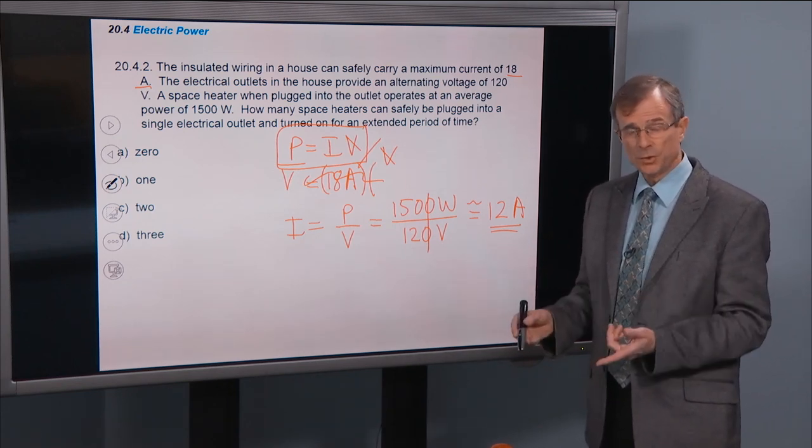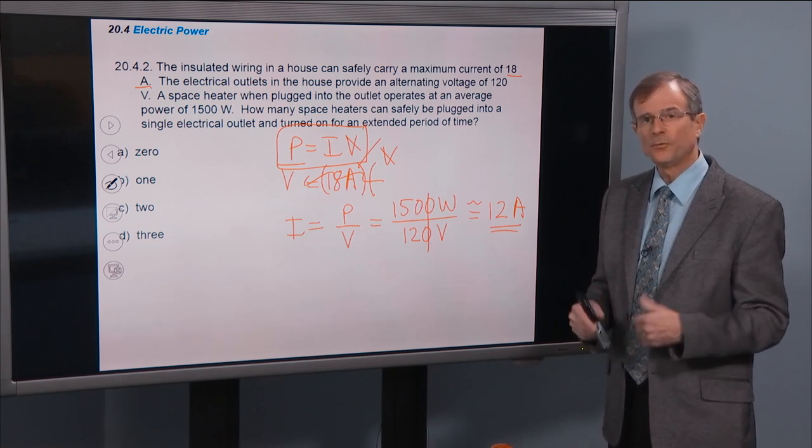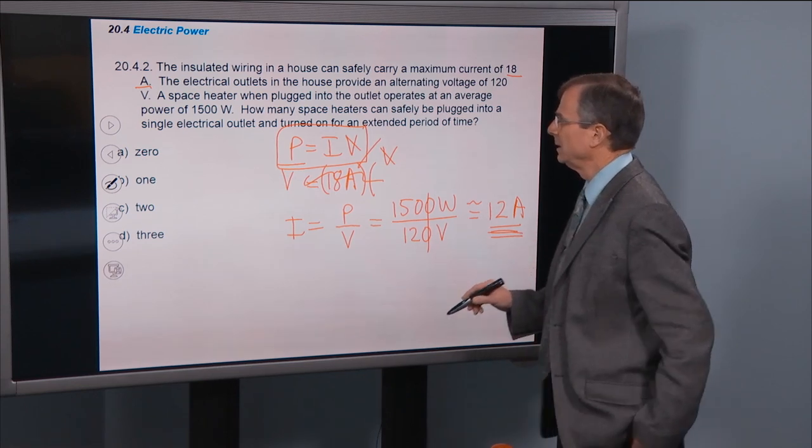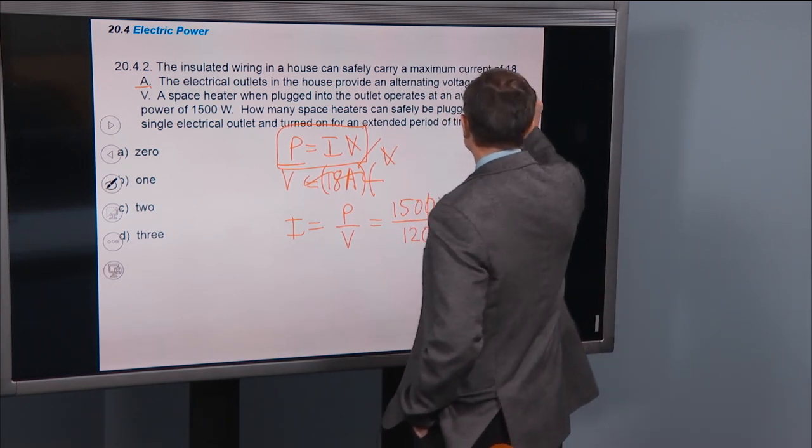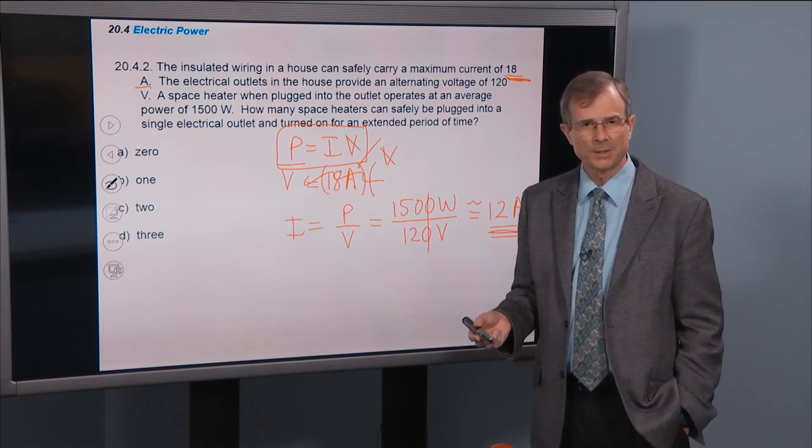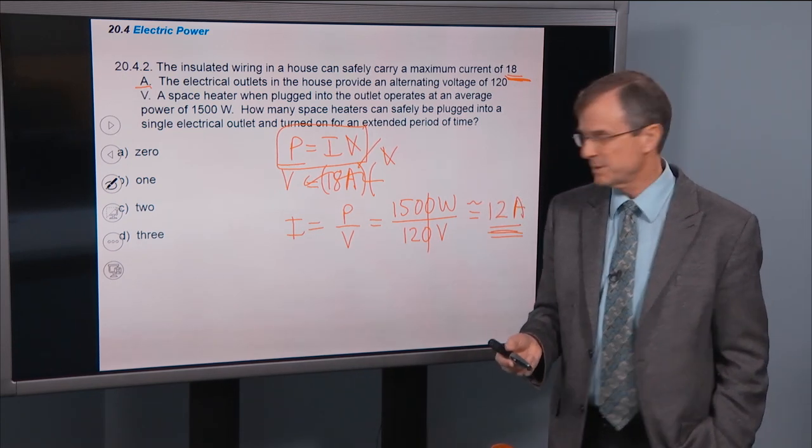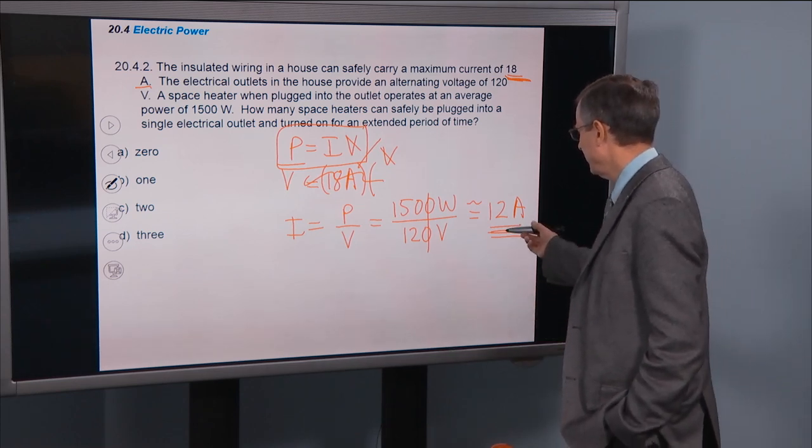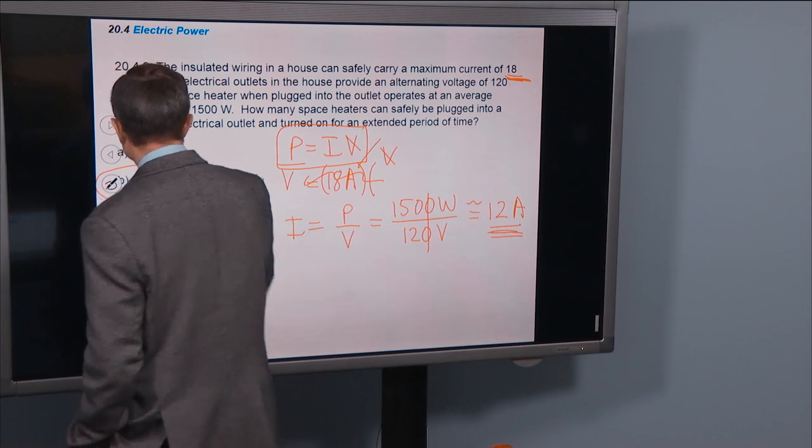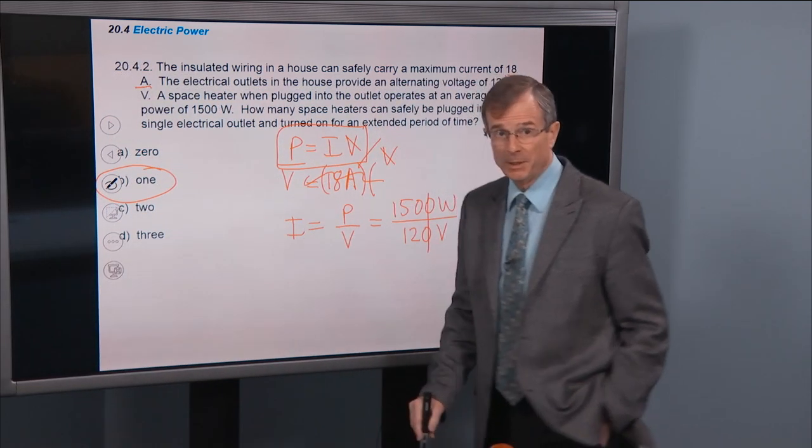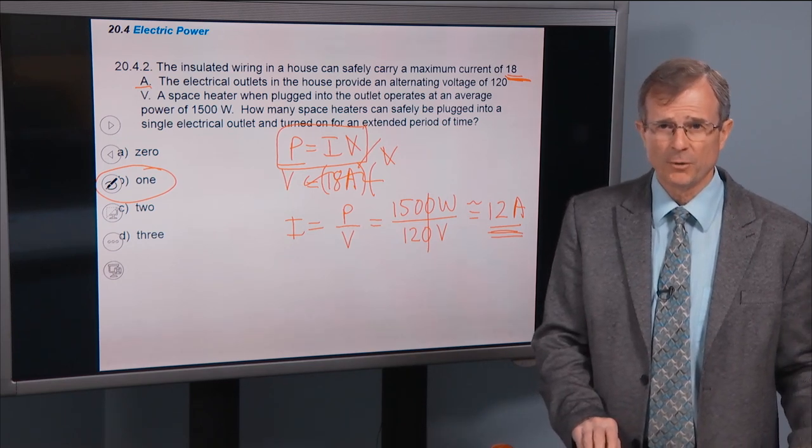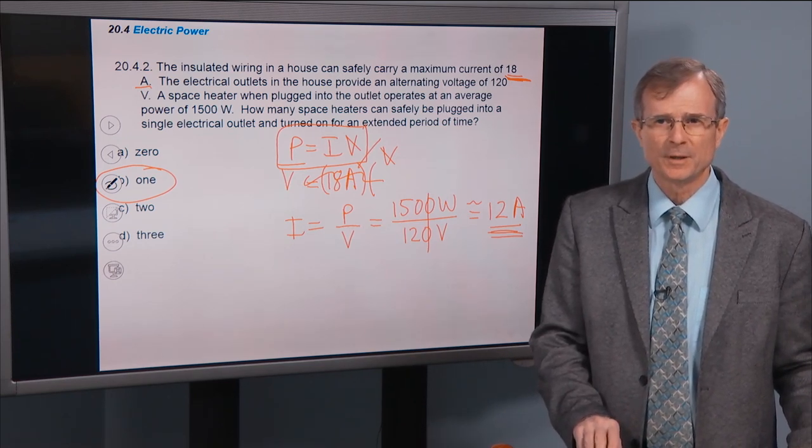If you put two of them into the circuit, you're going to draw double that current. And if you double this current, then you're in the danger zone. Because your circuits can only handle 18 amps. And twice this would be 24 amps. So you can really only safely put one space heater on that circuit if they have a power of about 1500 watts.